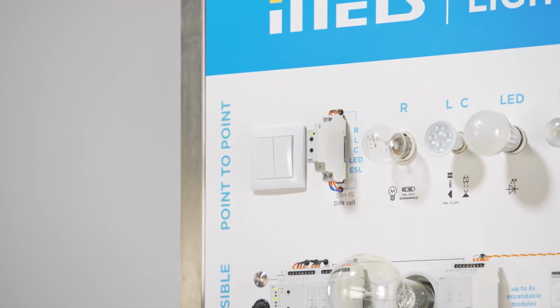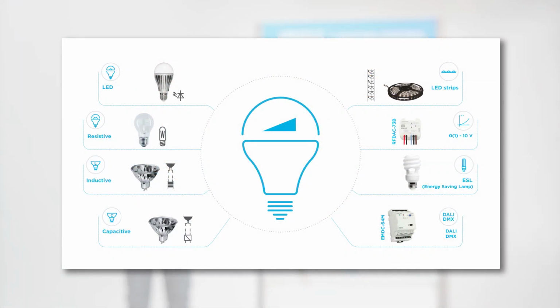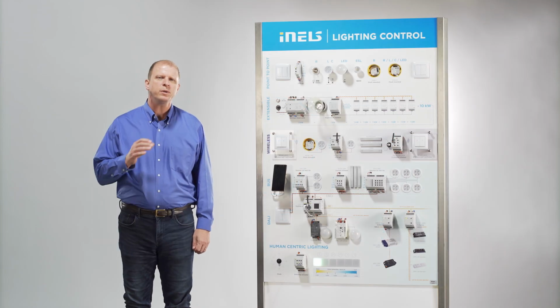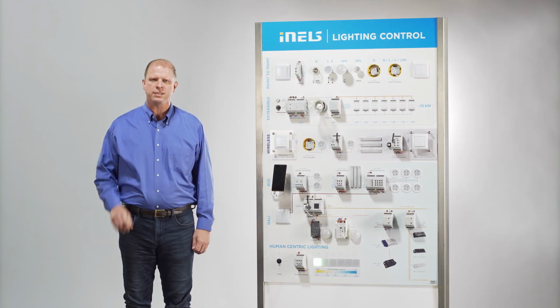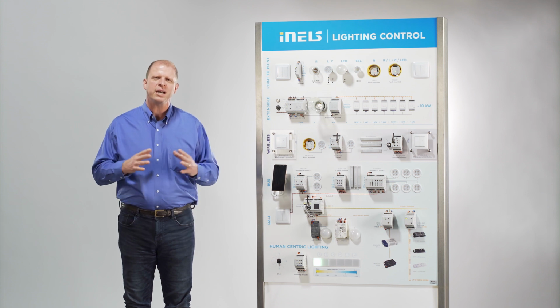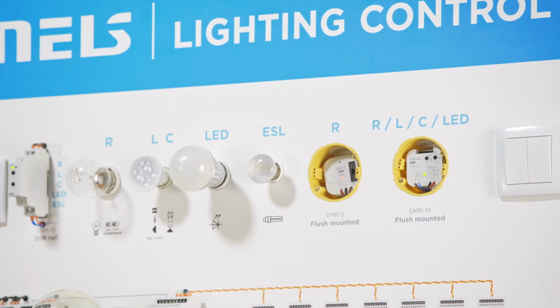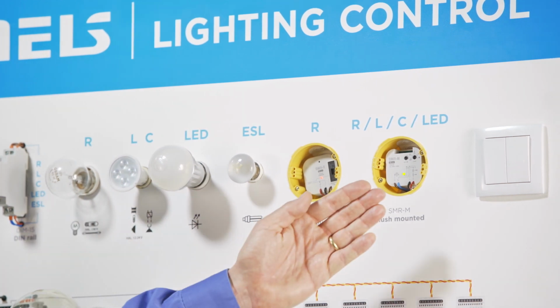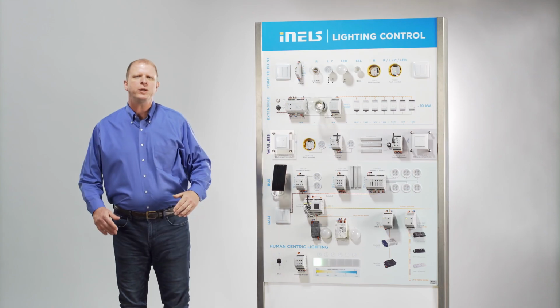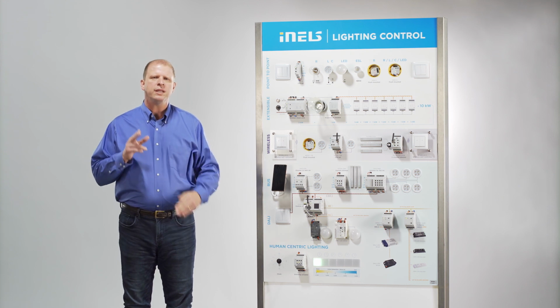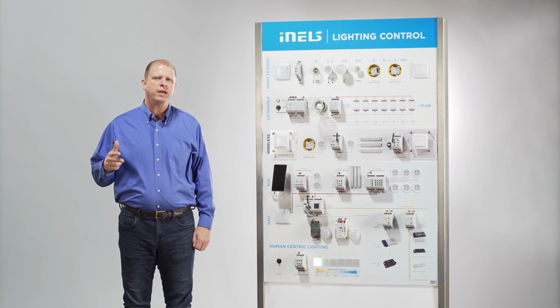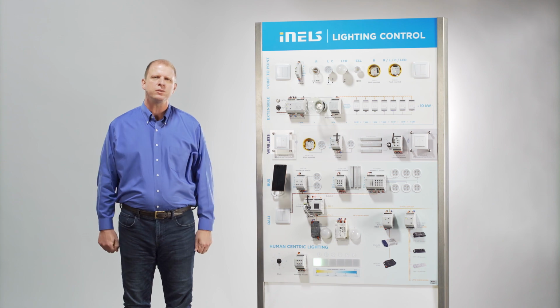Each of them is able to control a different range of loads, such as a dimmer module for a DIN-railed switchboard, which is able to dim the load up to 300 watts with a minimum control pulse length of 80 milliseconds, which is also suitable for fast actions. Our offer also includes dimming actuators designed for installation in electrical installation boxes and can be located near the control element. These boxed units have a last set memory and are capable of dimming various types of loads.